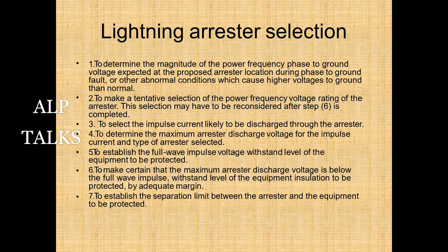Lightning arrester selection steps: determine the magnitude of power frequency phase-to-ground voltage expected at the arrester location during phase-to-ground faults or other abnormal conditions; make a tentative selection of the power frequency voltage rating; select the impulse current likely to discharge through the arrester; determine maximum arrester discharge voltage for the impulse current and type selected; establish the full-wave impulse voltage withstand level (BIL) of the equipment to be protected; verify that the maximum arrester discharge voltage is below BIL by an adequate margin; and establish the separation limit between the arrester and the equipment.